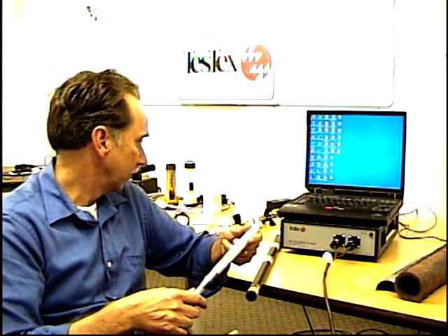Basically what this is sensitive to is any type of pitting or cracking that might be going on in the tube. We also have a single channel probe, which we also use. That's usually for general wall loss in boiler tubes, heat exchangers.